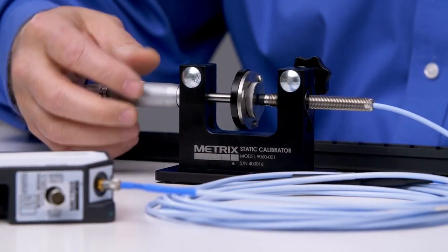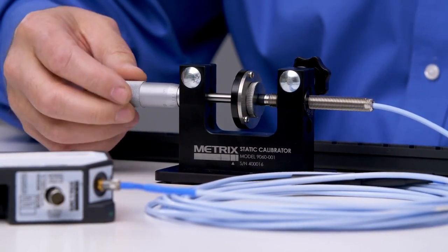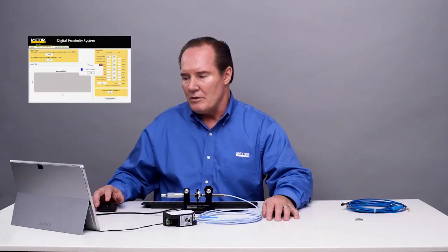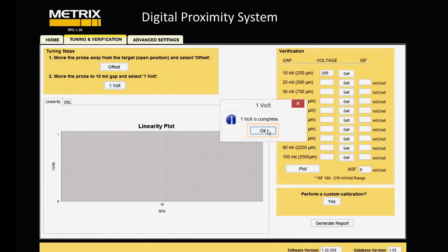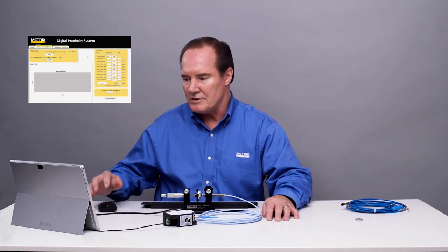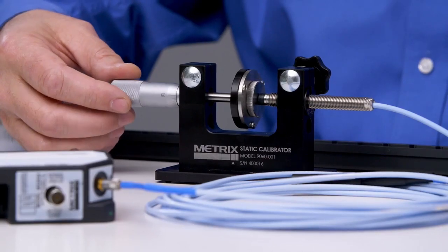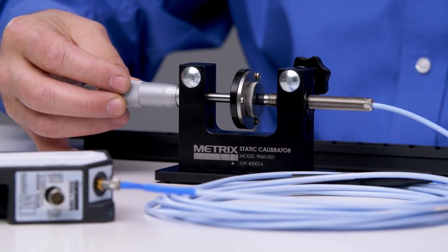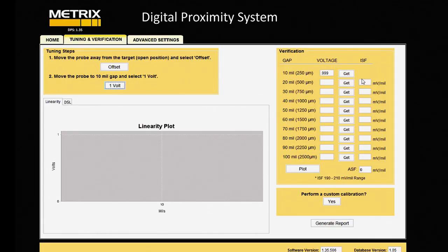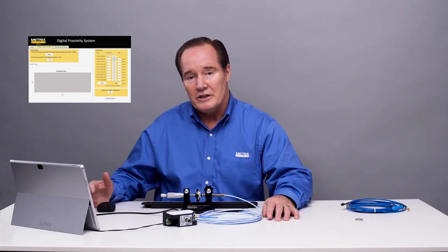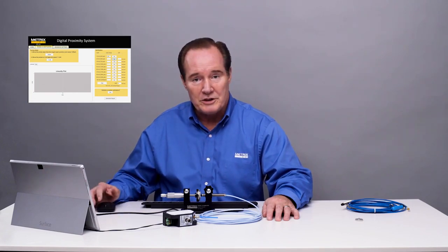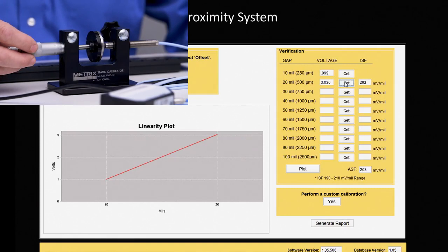And what this does, it just helps with the linearization of the system. So we'll capture the voltage at 10 mils. It's 0.999, very close to 1, which is good. And then we'll do it in 10 mil increments. We'll record voltages and just see how linear the system is. And if it's not perfectly linear, we'll go ahead and do a custom calibration, but we'll see how it does.